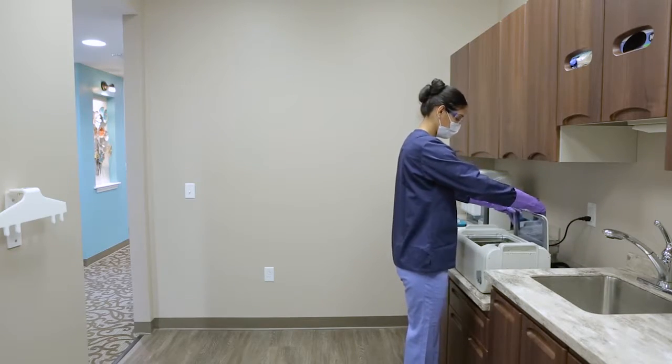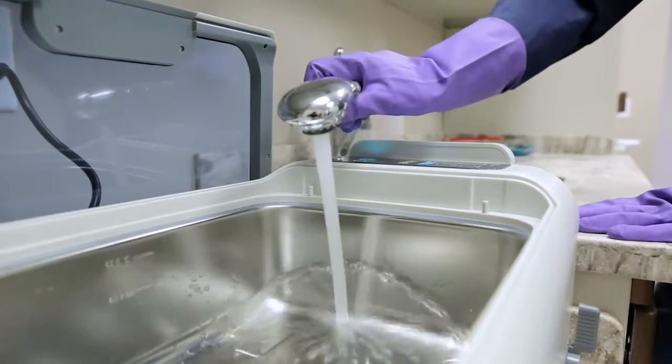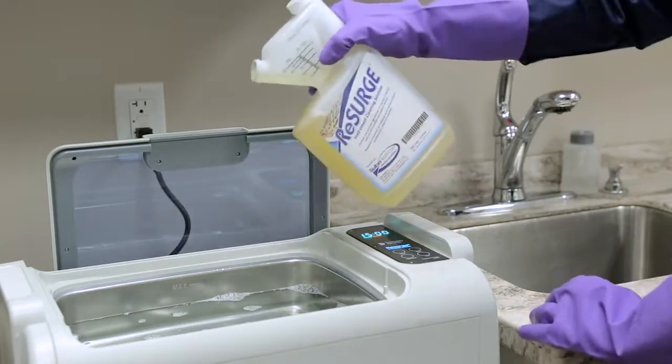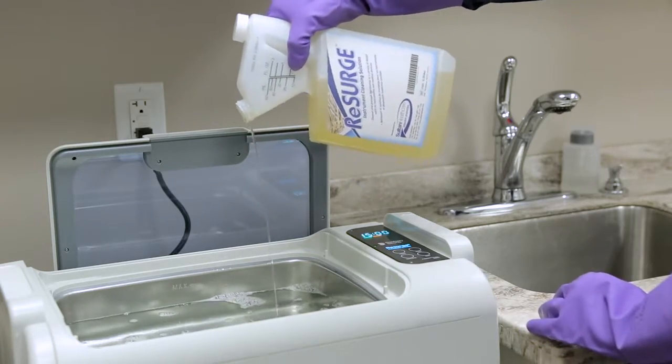Fill the Resurge ultrasonic cleaner with fresh water to the minimum fill line. Add Resurge instrument cleaner as directed in the instructions for use.